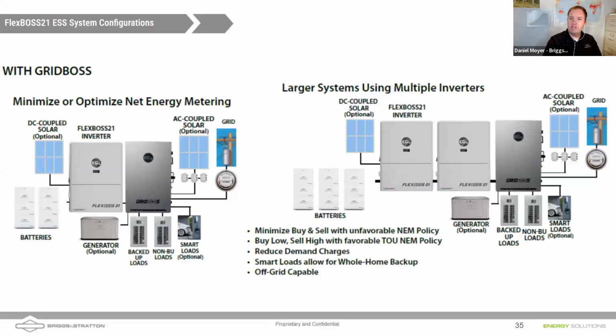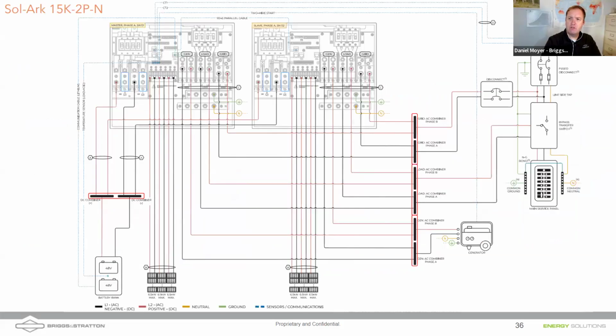On the right, we see a multi-inverter system coming into that Grid Boss. That is the key, really, because there are a lot of parts and pieces that the Grid Boss offers when we compare it to, say, a Sol-Ark, for example. I'll show you what I mean by that right now. There's a lot going on this screen, but what we're looking at is two paralleled Sol-Ark 15K systems. In the top right corner, we have grid coming through a utility meter, going into a disconnect.